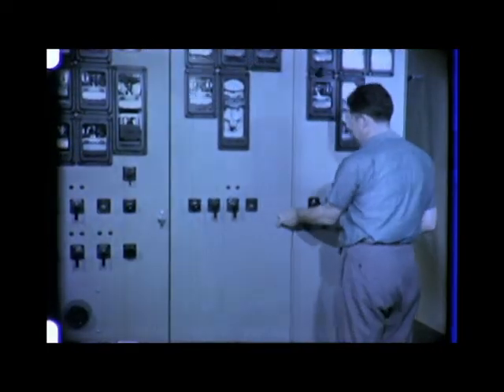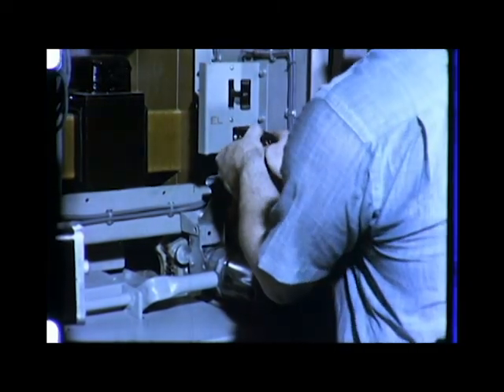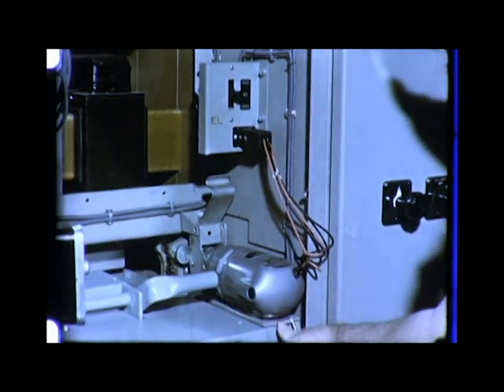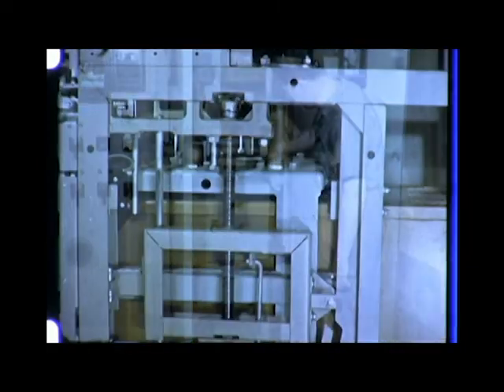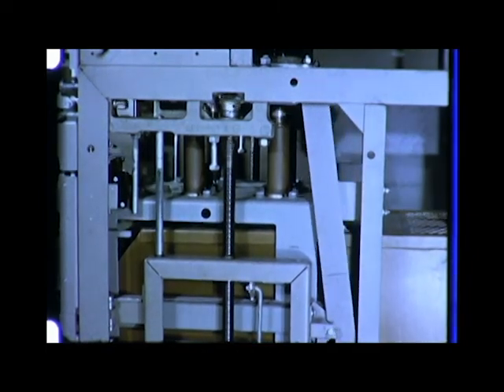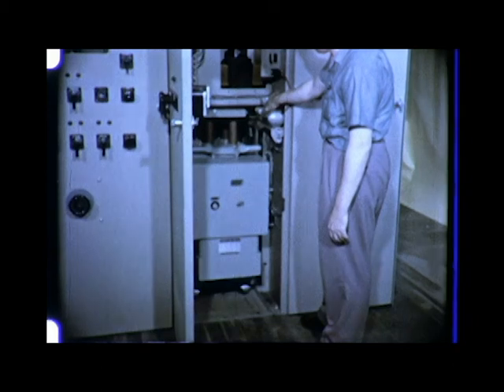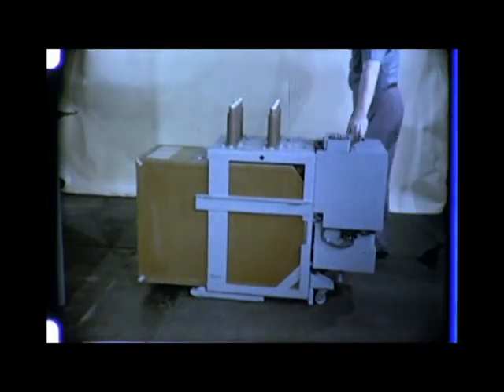The vertical lift design of metal clad enables a Magne-Blast breaker to be disconnected quickly and safely. A motor-driven elevating mechanism raises and lowers the breaker with negligible effort on the part of the operator. As the breaker disconnects, stationary high voltage parts are automatically barriered off by a shutter operating arm that does not rely on gravity. The operator can actually see the circuit breaker disconnect from the high voltage circuit. Simple, rugged female disconnects remain protected in the stationary structure and are never exposed to accidental damage. Metal-clad switchgear is built to give long years of service, but if and when maintenance is necessary, the job will be easy and can be handled by one man. While the breaker is being removed, its low center of gravity eliminates the hazard of tip-over.